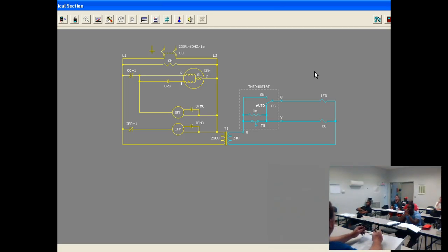I only have one line voltage. This line voltage here, let's see, I have a crankcase heater, I have a compressor, a capacitor, a single contactor on that, it's not a double pole. I have an indoor fan relay on my indoor fan motor. Let's see, outdoor fan motor, capacitor for both, a transformer signal, a simplified thermostat. I have an IFR. They like to use the solenoid symbol, not the coil symbol. But IFR is my indoor fan relay, CC is my contactor coil.